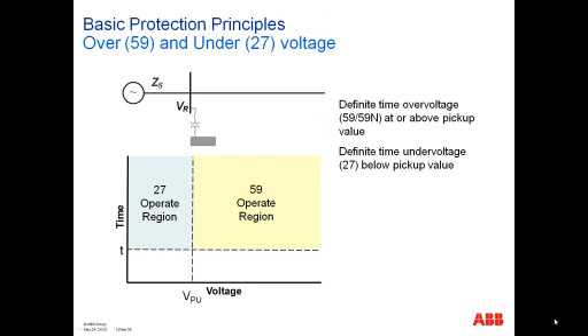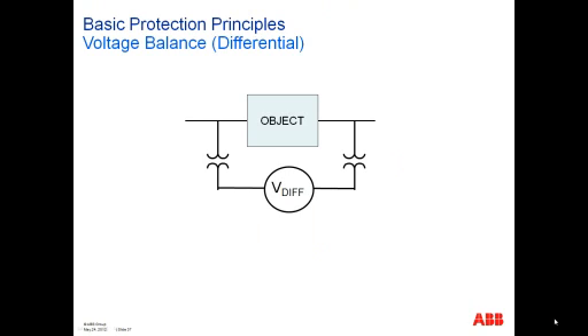Then you have overvoltage and undervoltage protection, and that basically shows you the two operating regions. You have your voltage pickup level. If it's an undervoltage relay, it operates where the voltage is under that value, or it operates where the voltage is over that value. And you also have a voltage balance, where you measure the voltage on each side of an object, and this is quite often used in capacitor bank protection. You measure the voltage at 2 points and measure their difference, which shows the voltage drop across the object.